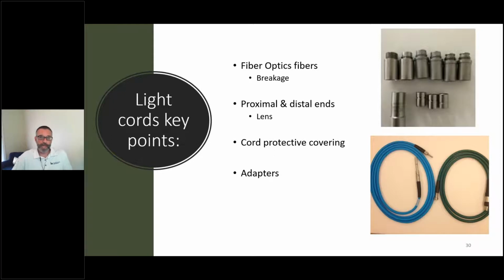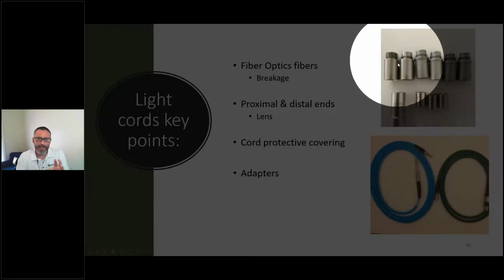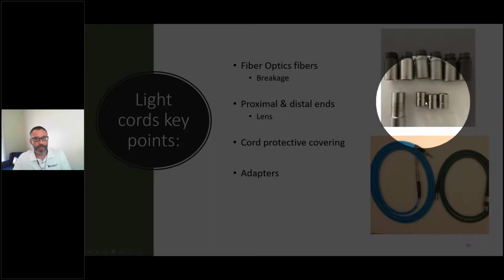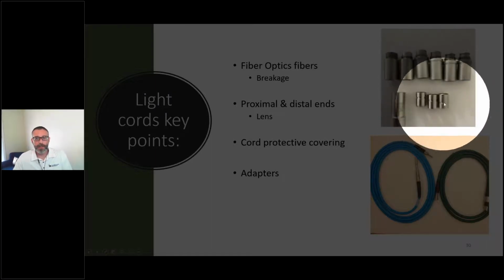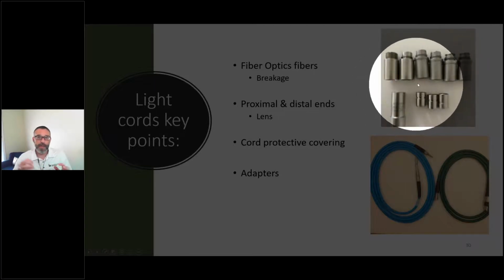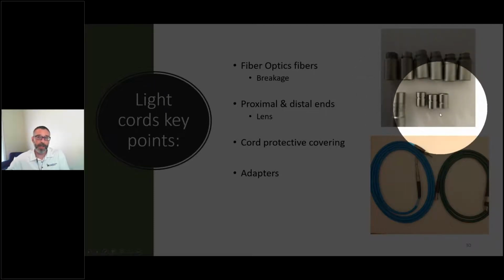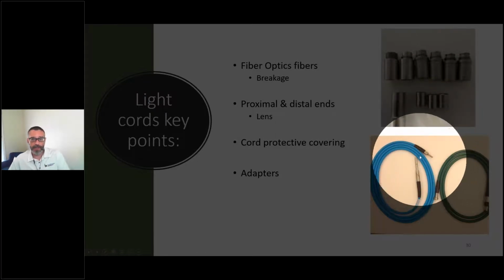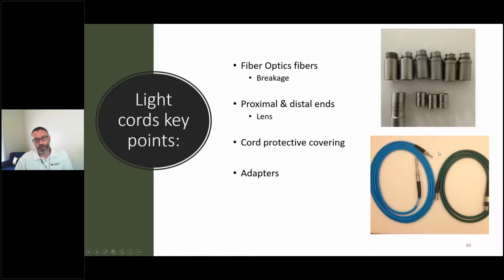And then the myriad of adapters. If you have a scope that has an inner adapter and an outer one, and somebody says, I don't need that little inner one, you should take a look at the IFU, because actually you may need it. These things go together, and depending on the light source up in the operating room, they may need that inner one to connect to it. So please don't shortchange the adapters or throw on whichever one you've got, because they may get it in the OR and it may not hook up to the light source, or it may not hook up to the scope.